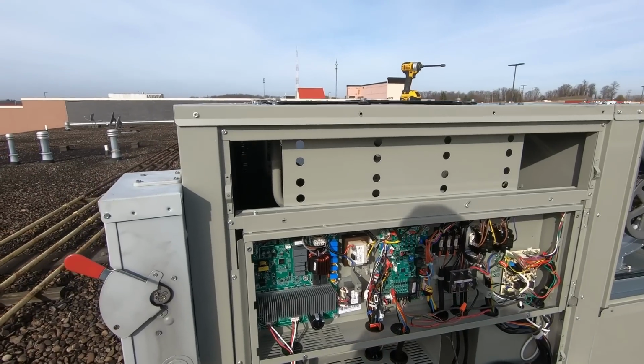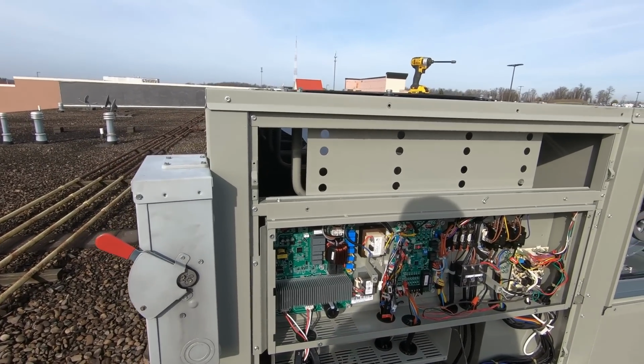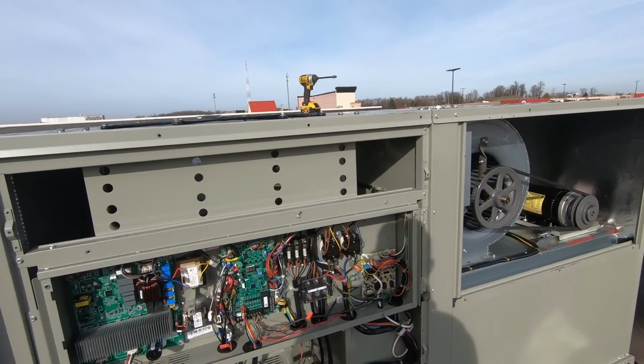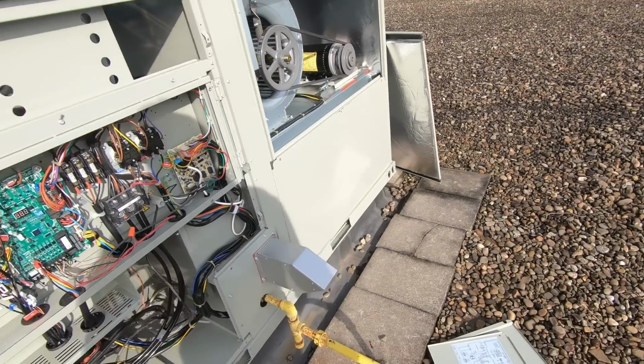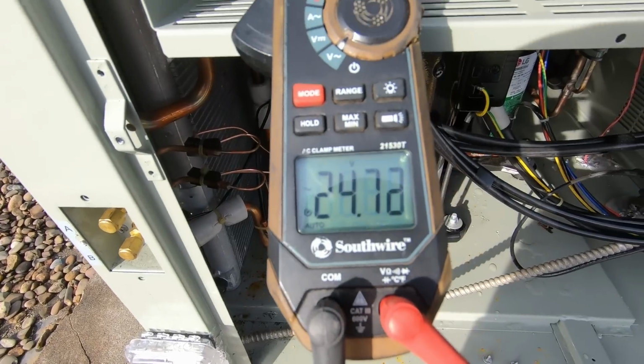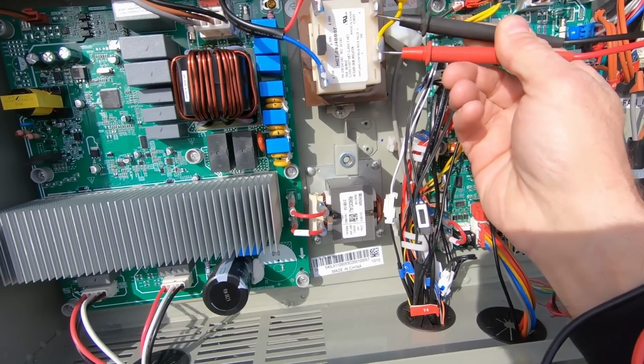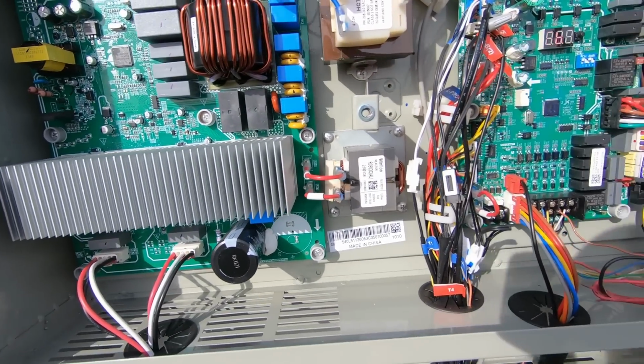I'm going to check and make sure we have 24 volts coming out of our transformer and start tracing it out, and look at the wiring diagram of course. All right, we do in fact have 24 volts from our transformer.